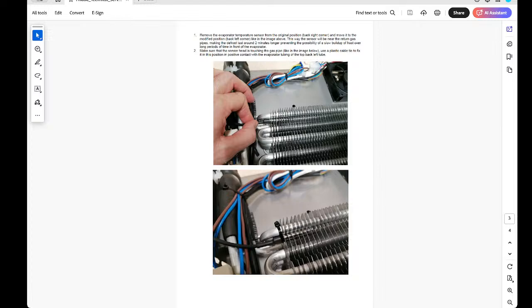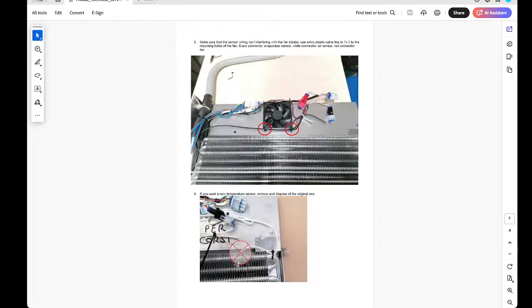So here's the sensor placement. The new placement is going to be on the top left of the evaporator. They want you to do it nicely. Use a nice little zip tie to hold it in place so that it doesn't move. It's going to build ice on that evaporator, and when it builds ice, it's going to move that sensor around. So make sure you zip tie it in place so that it always reads the correct temperature. We need the precise temperature in that placement so that the sensor reads well, so that it goes through a proper and long enough defrost so we don't have too much ice built up after the defrost cycle is complete.